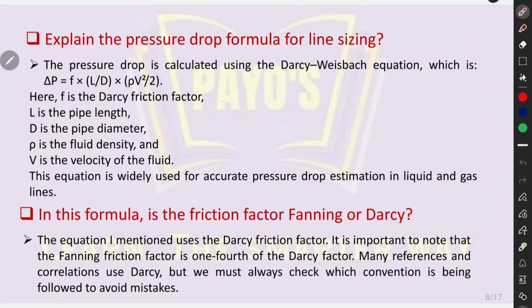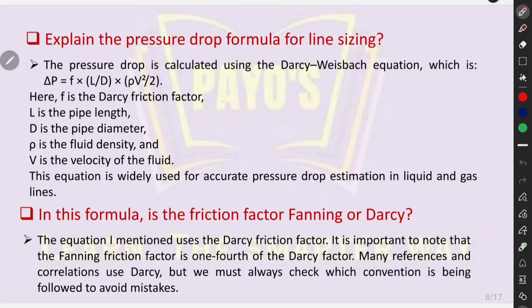Can you give me the pressure drop formula for line sizing? The pressure drop is calculated using the Darcy-Weisbach equation: ΔP = f × (L/D) × (ρV²/2), where f is the Darcy friction factor, L is pipe length, D is pipe diameter, ρ is fluid density, and V is velocity of fluid. This equation is widely used for accurate pressure drop estimation in liquid and gas lines. It is important to note that the Fanning friction factor is one-fourth of the Darcy factor. Many references use Darcy, but we must always check which convention is being followed to avoid mistakes.